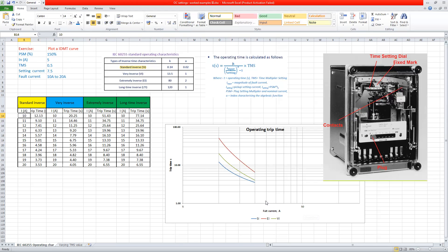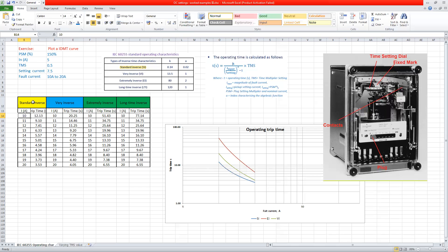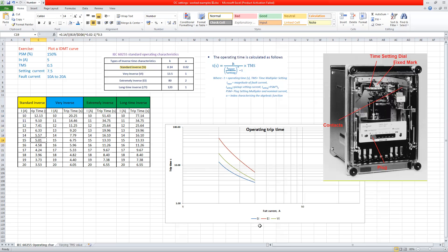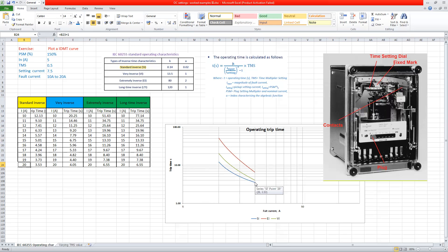So if we do that way, then when the fault current is 10, so for example, now we have 10. So the fault current is at 10, then the trip time will be 12.13 seconds. So for example, if you see at 10, it's 12.13, as you can see. So this is for the standard relay. And then at 20, for example, this varies, and at 15, it is 5. So at 15, what can I find? That's 10, that's 15. So at 15, if I put my cursor here at 15, it's 5.01. That is the same. And then at 20, it's 3.53. So if I plot at 20, it's 3.53, which is this one.